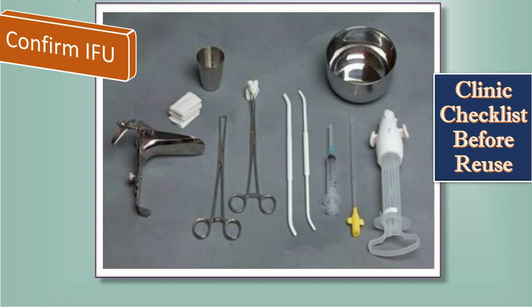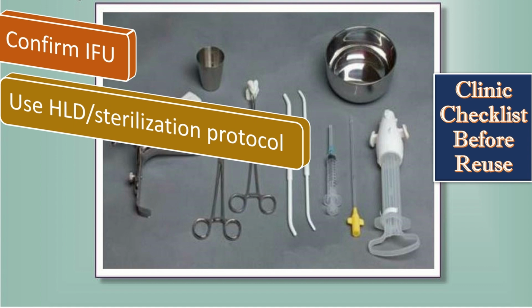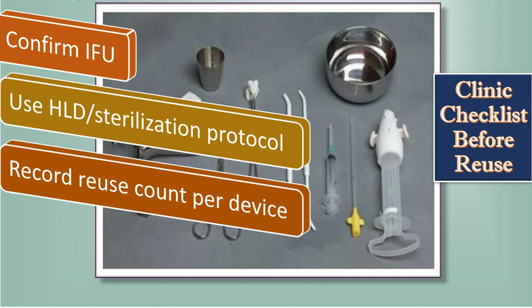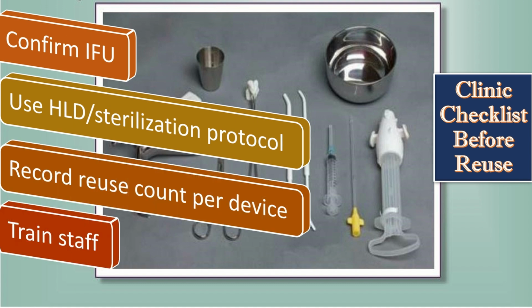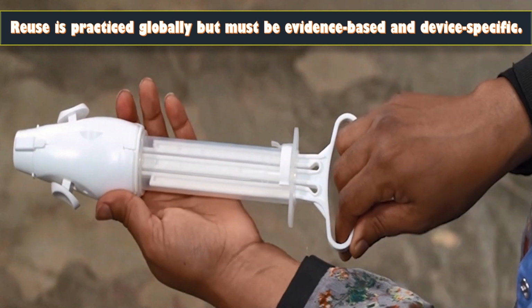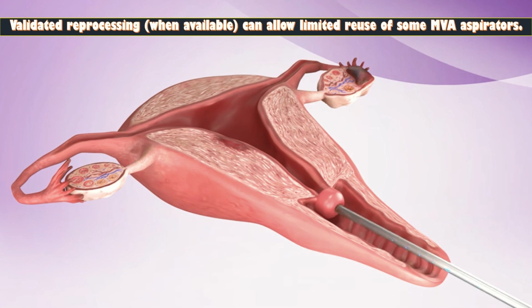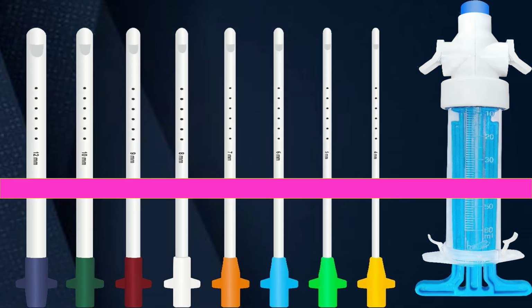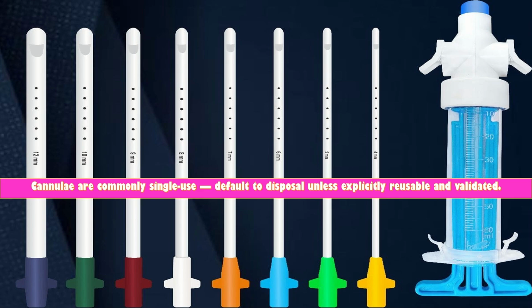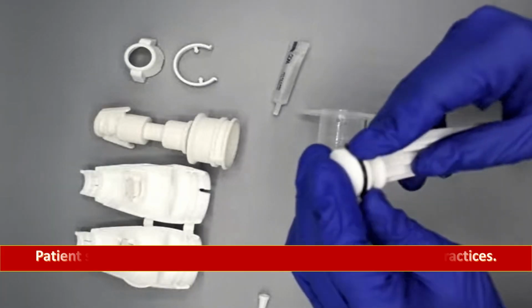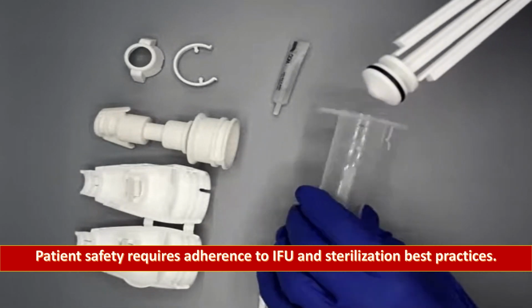The cleaning checklist before reuse includes: confirm the IFU for the model and batch; use a validated cleaning, HLD, or sterilization protocol, which should be documented; record reuse count per device and visual inspection notes; train staff and perform periodic competency checks. Reuse is practiced globally but must be evidence-based and device-specific. Validated reprocessing, when available, can allow limited reuse of some MVA aspirators. Cannulae are commonly single-use, so default to disposal unless explicitly reusable and validated. Patient safety requires adherence to IFU and sterilization best practices.